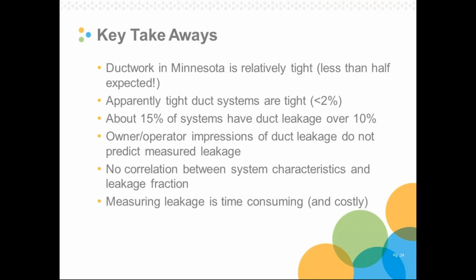The key takeaways from our experience measuring duct leakage in all these systems is that sheet metal ductwork in Minnesota is pretty tight, tighter than we expected. Based on the work in California, we were kind of looking for about 15% average duct leakage, and we found less than half that, about 7%. The second thing we learned is that apparently tight duct systems are tight. This means if it looks sealed and the sealing is holding up, it's probably going to be pretty tight. And then there are certain sheet metal types of construction like spiral, welded, flange and gasketed ductwork that generally are tighter than regular sheet metal construction.